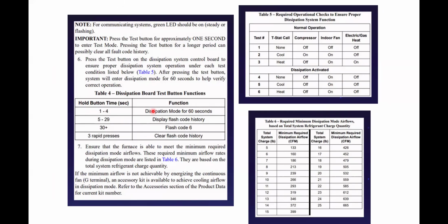By the way, we did the two in Melrose Park last, I don't know, May or June. Two different guys installed it from the same contractor, both like 15 years experience. Both of them wired it wrong. Granted, they didn't come to the class. They probably didn't read the book, but they both wired everything wrong. Everything was working. They thought it was all working. Heat function, cooling function. They charged the unit. When I pressed the test button, nothing shut off.